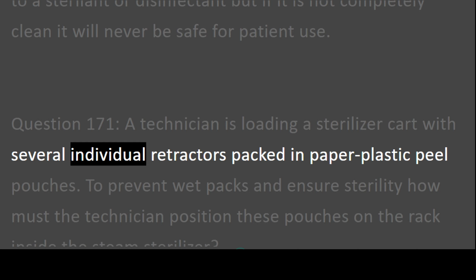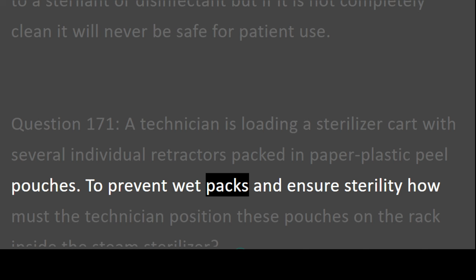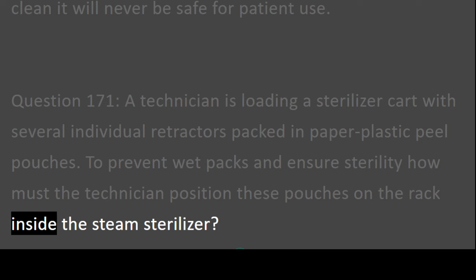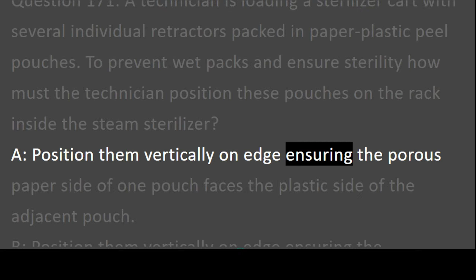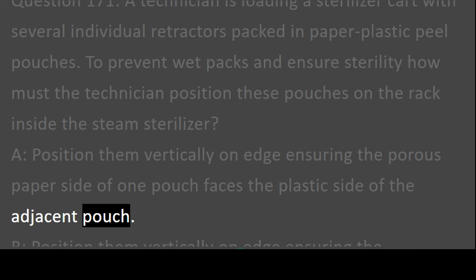Question 171. A technician is loading a sterilizer cart with several individual retractors packed in paper-plastic peel pouches. To prevent wet packs and ensure sterility, how must the technician position these pouches on the rack inside the steam sterilizer? A. Position them vertically on edge, ensuring the porous paper side of one pouch faces the plastic side of the adjacent pouch. B. Position them vertically on edge, ensuring the transparent plastic side of one pouch faces the plastic side of the adjacent pouch.